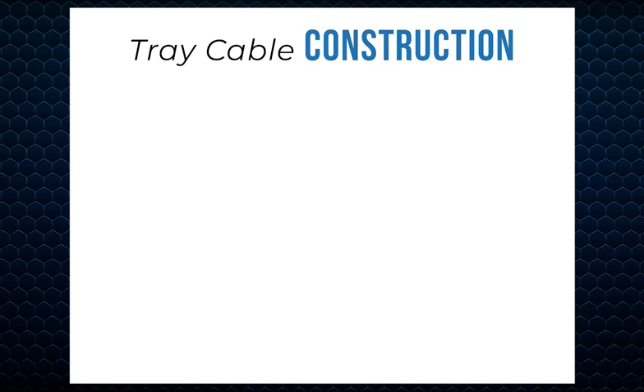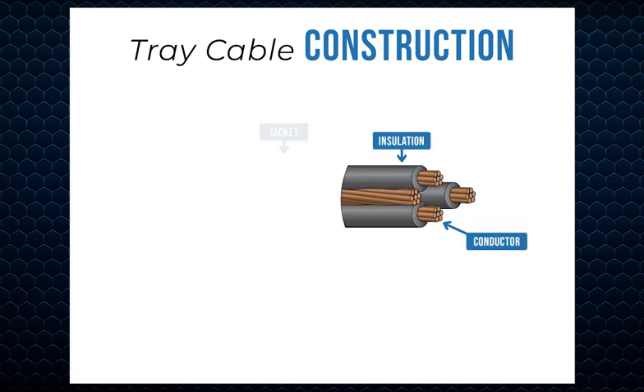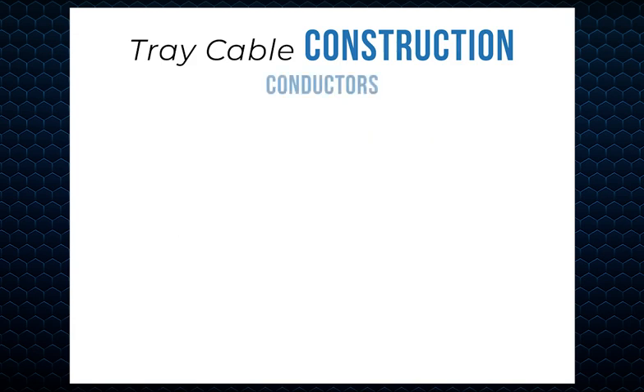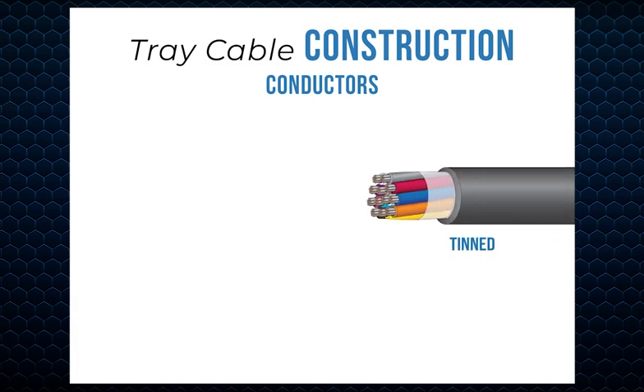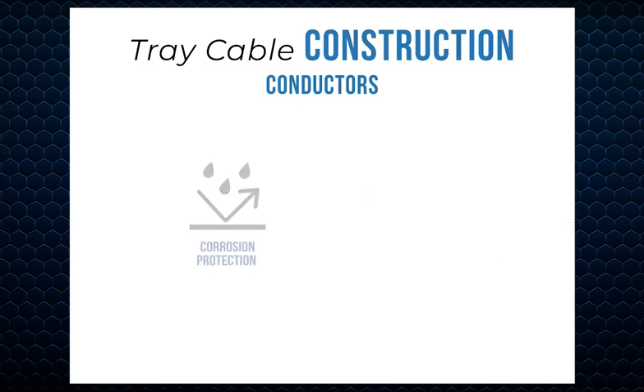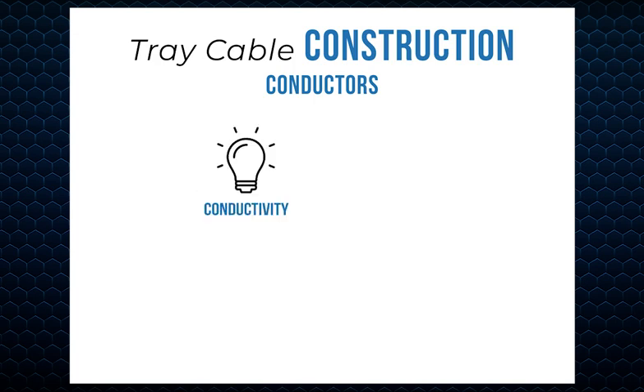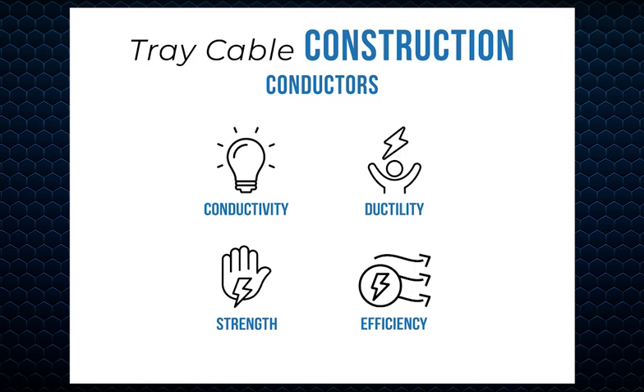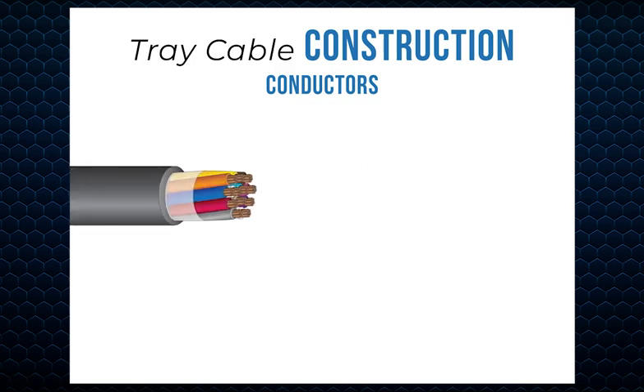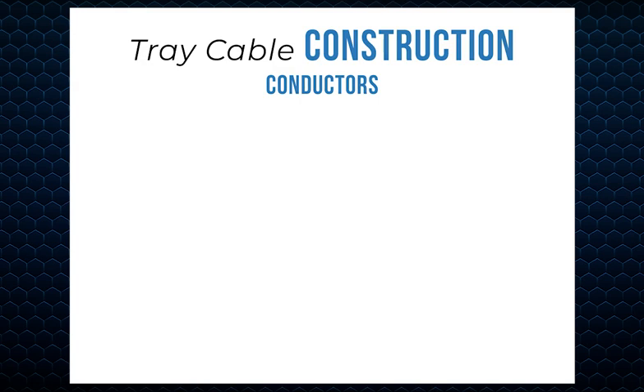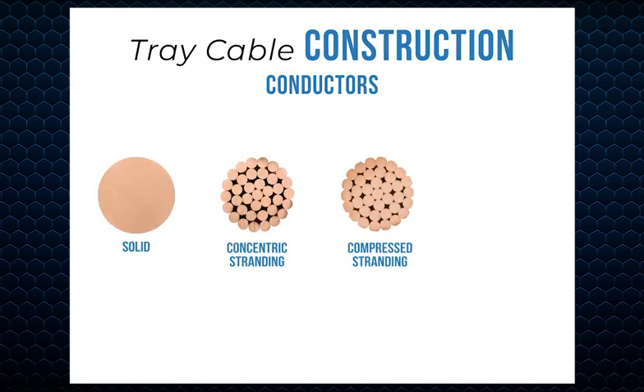Service Wire tray cable is made of 4 components: inner conductors, insulation, jacket, and an optional shield. Tray cable conductors are most commonly copper, but they can be tinned copper. Tinned copper conductors are primarily used for both corrosion protection and ease of soldering. Copper's combination of conductivity, ductility, strength, and efficiency make it the optimal conductor of choice. Service wire manufactures both bare and tinned copper conductor tray cable. There are 4 different conductor types: solid, concentric stranding, compressed stranding, and compact stranding. Conductors have lower electrical resistance, smaller diameter, and are more efficient when the gaps between each strand are smaller. However, the more compacted the strands, the less flexible the cable. Popular twist options available for stranded conductors include concentric lay and unilay.